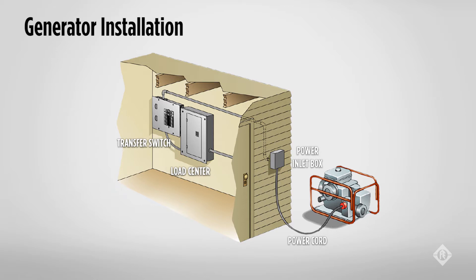When installing a generator, follow all local, state, and national electrical code requirements. A transfer switch is required by the National Electrical Code. A transfer switch is a safety device to isolate the utility electrical supply from the generator, to prevent the generator from back-feeding into utility lines, which can cause serious injury. A transfer switch should have a load applied, and it allows the load to be turned off and on independently of the generator. Code also requires that the generator be properly grounded per manufacturer's instructions.